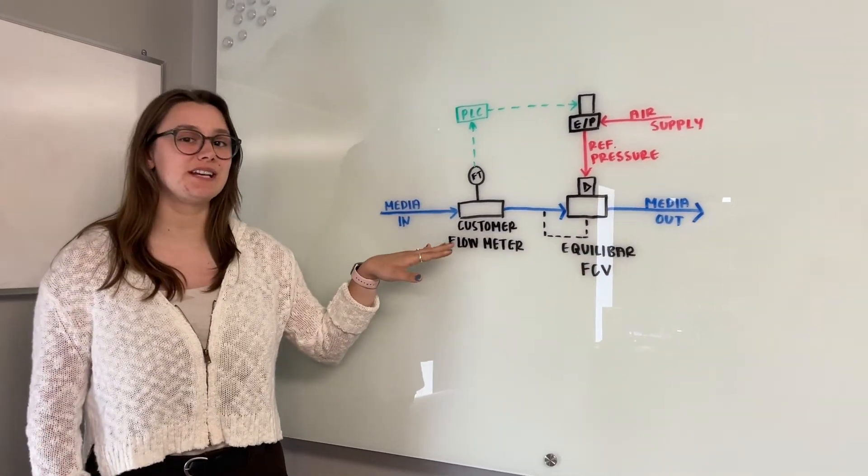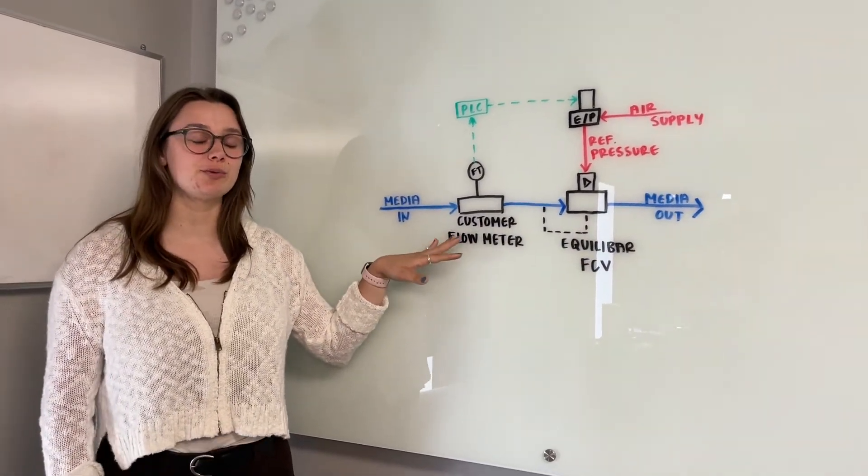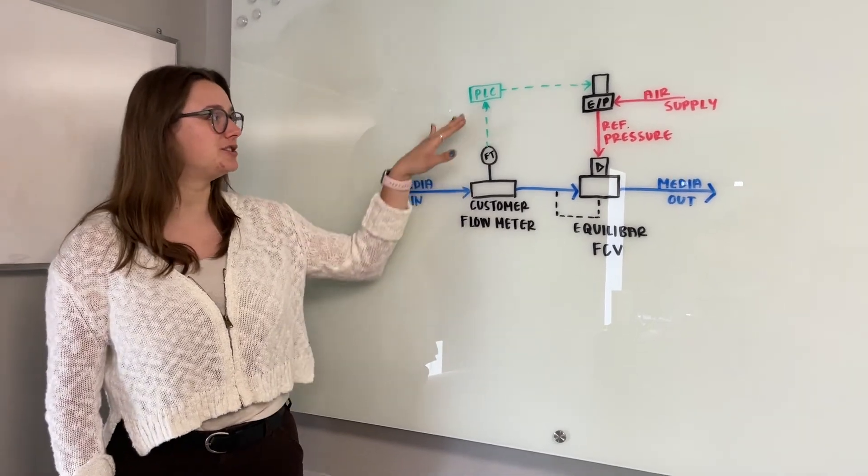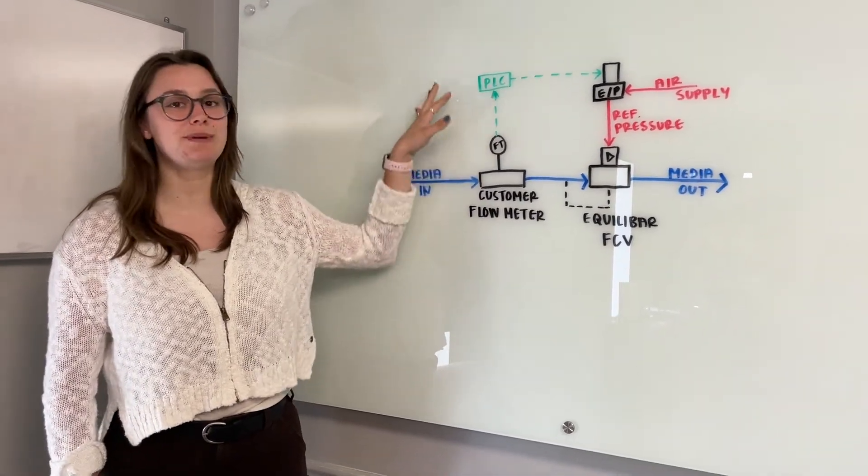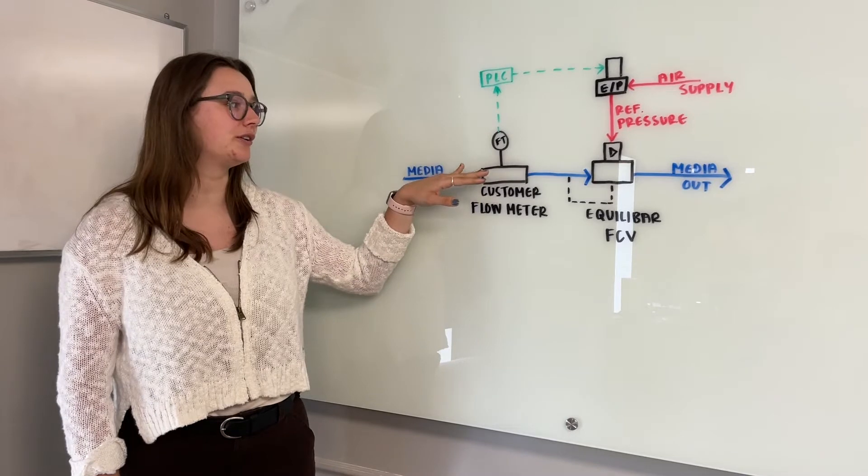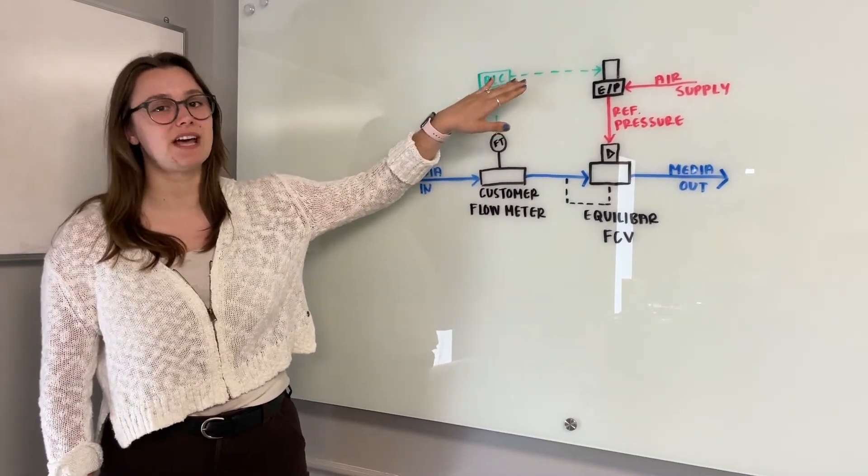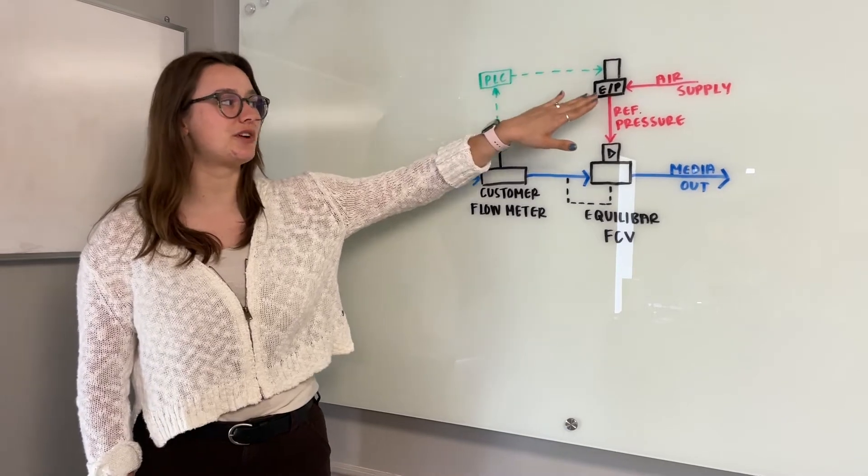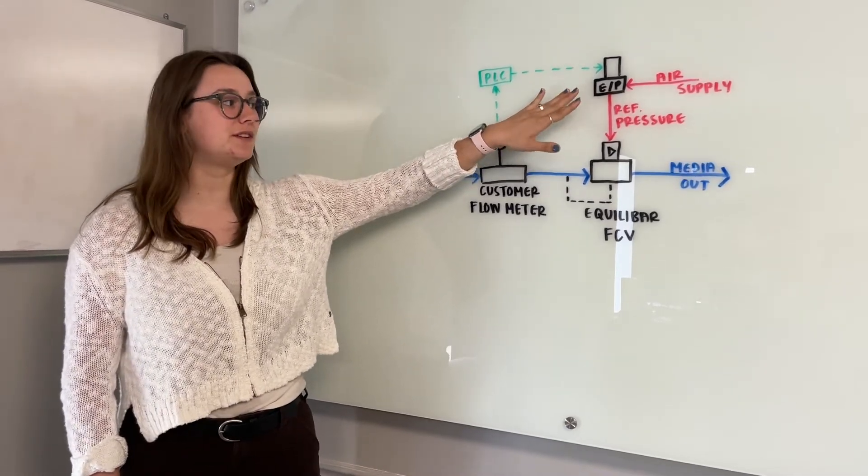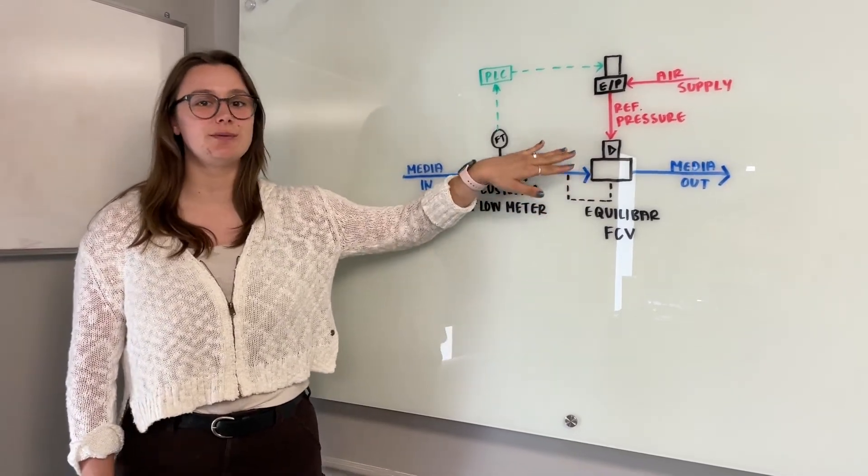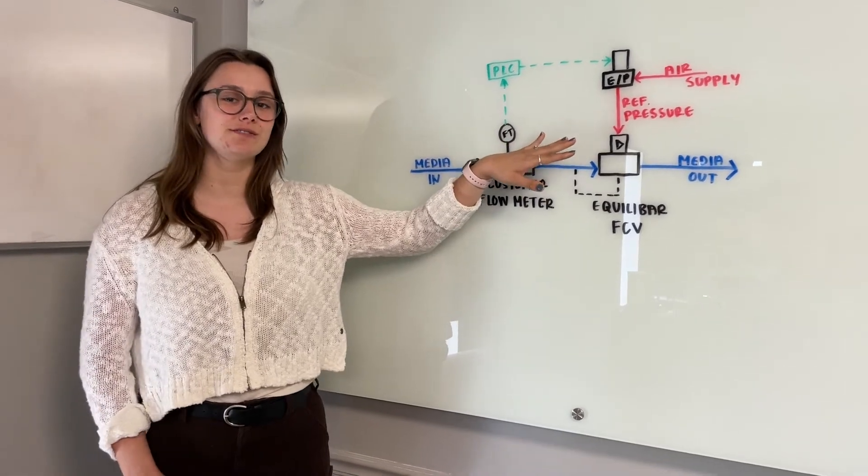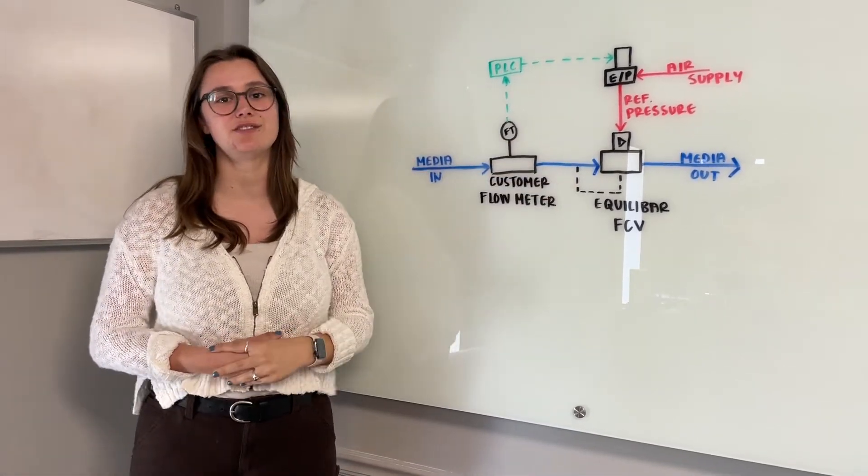The flow meter is translating the measured flow to a 4 to 20 milliamp signal which is going to the PLC, being run through a PID loop comparing the measured flow to the set point. That is translated to a 0 to 10 volt output signal which drives our QPV. The QPV will increase the pressure on the dome of the Equilibar to decrease the flow in the system and vice versa to increase the flow.